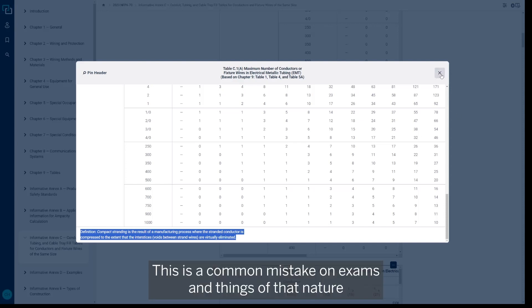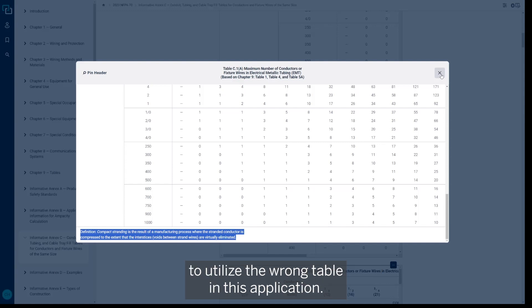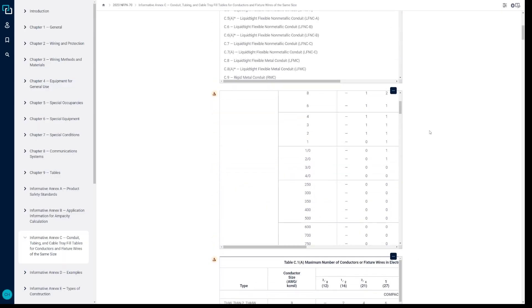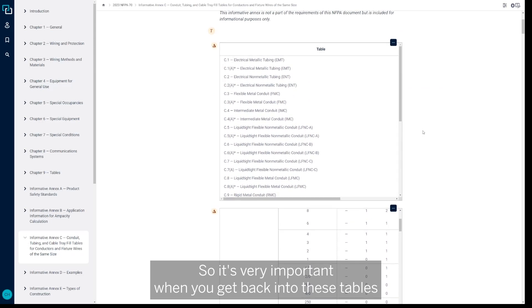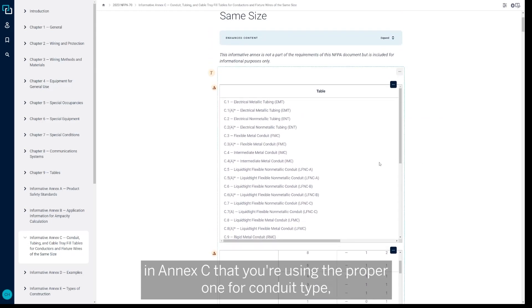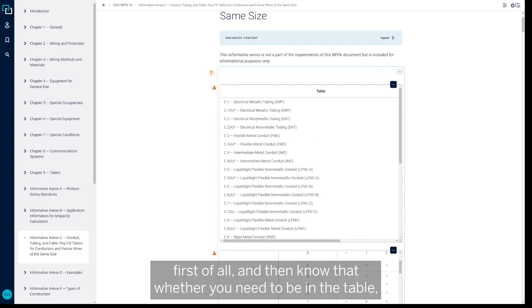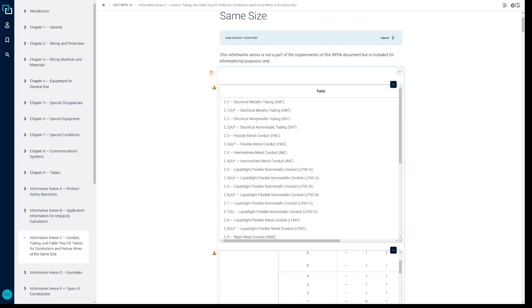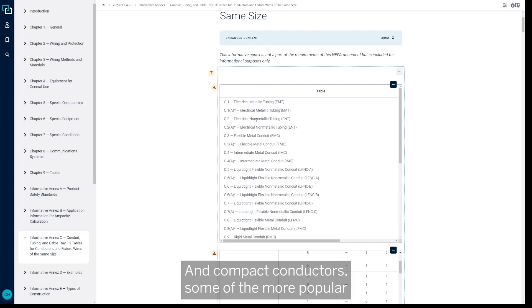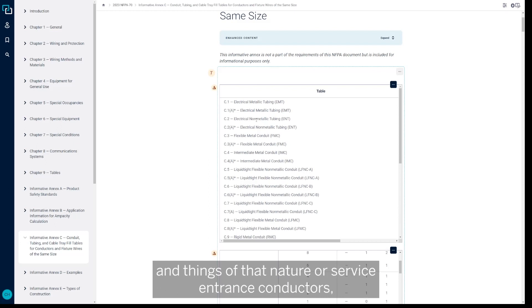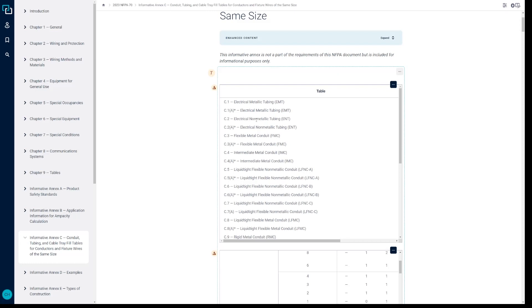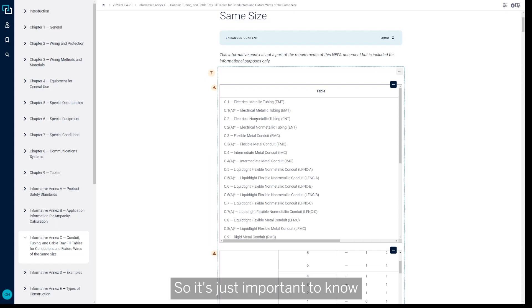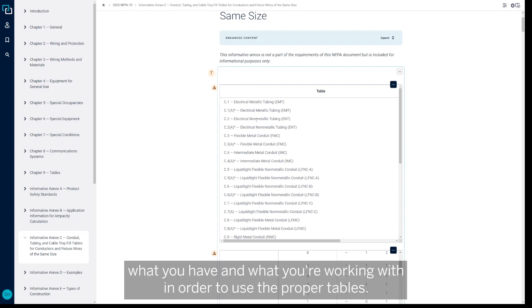This is a common mistake on exams and things of that nature to utilize the wrong table in this application. So it's very important when you get back into these tables in Annex C that you're using the proper one for conduit type first of all, and then know whether you need to be in the table that's for standard conductors or if you're using compact conductors. And compact conductors—some of the more popular aluminum wire that can be utilized for service entrance cables and things of that nature, or service entrance conductors—utilize that compact conductor manufacturing process. So it's just important to know what you have and what you're working with in order to use the proper tables.